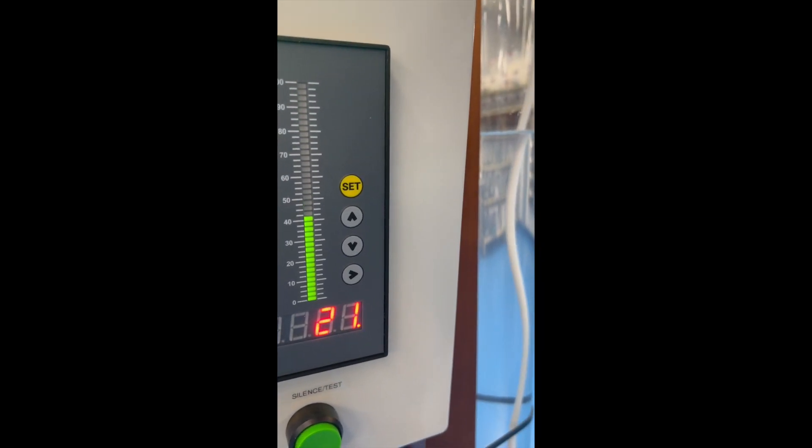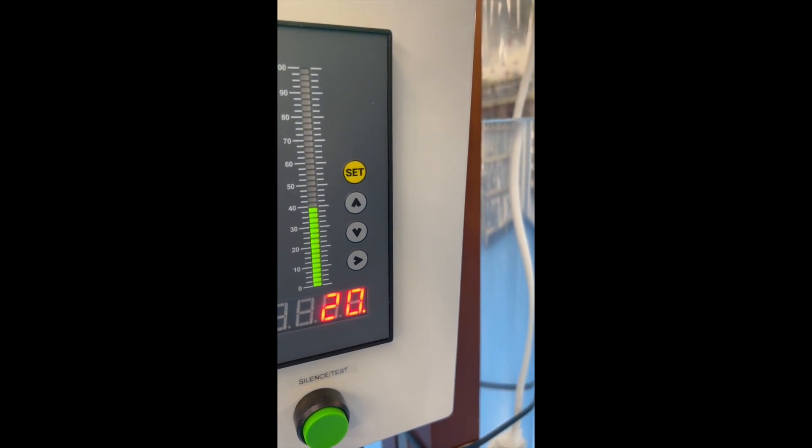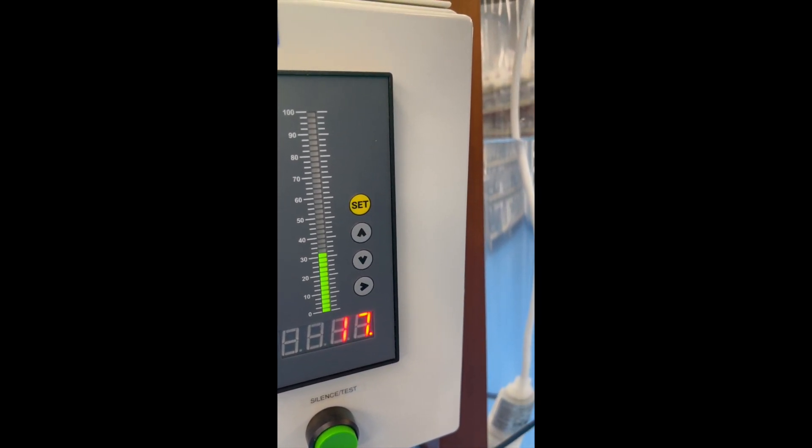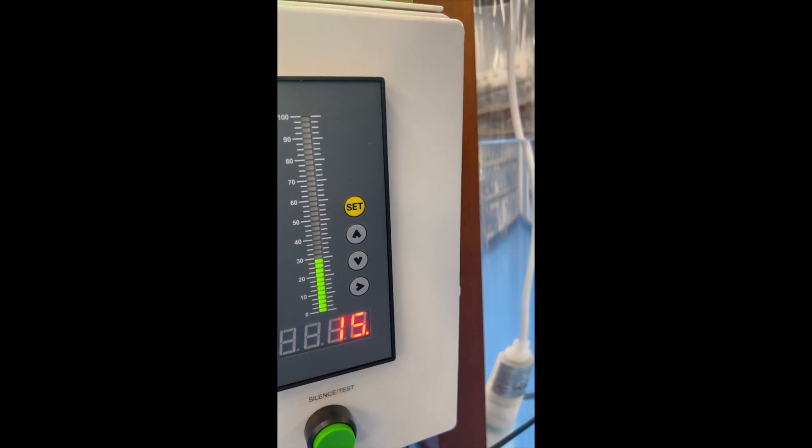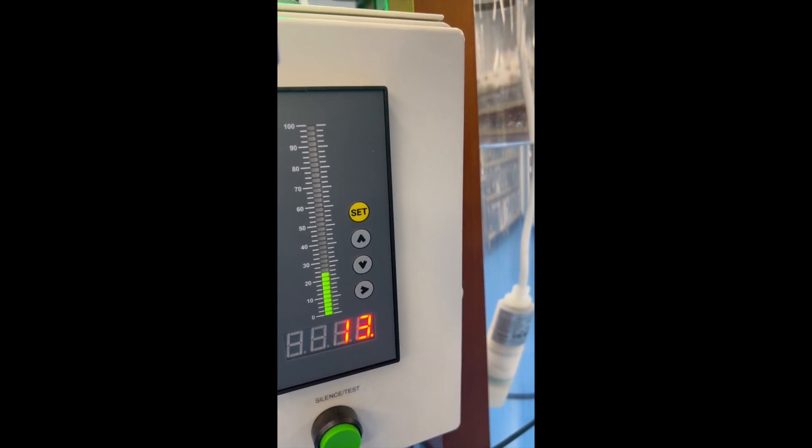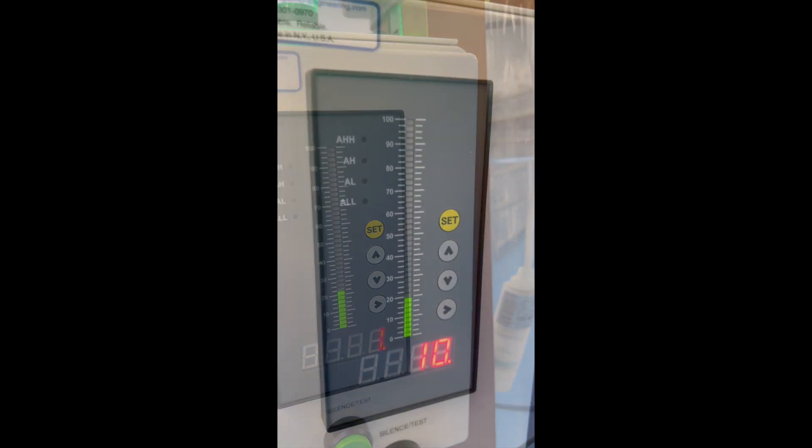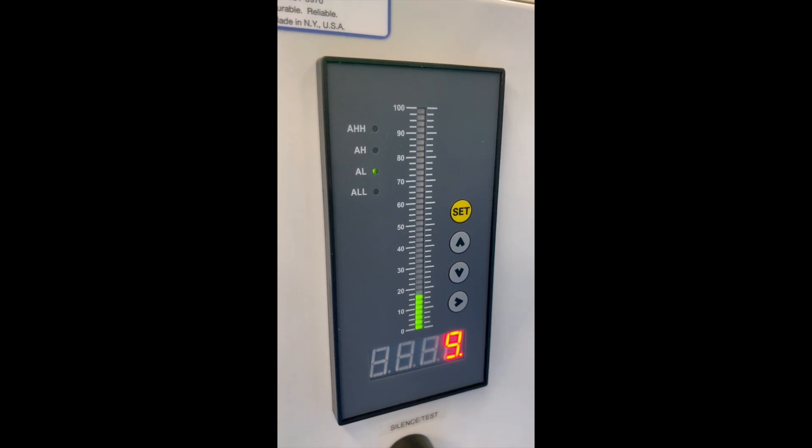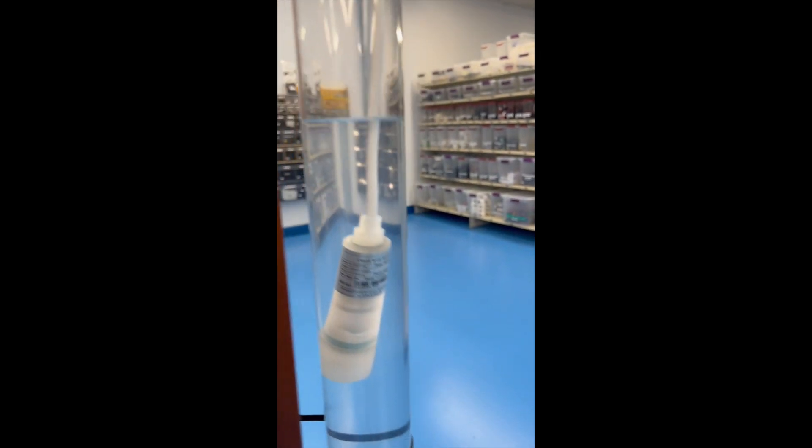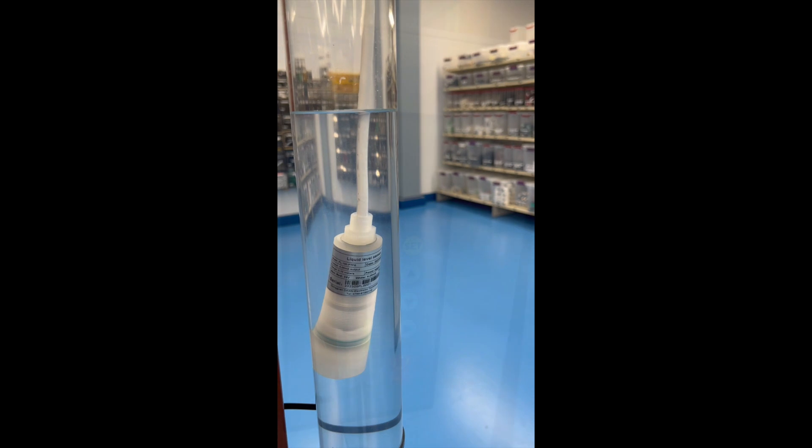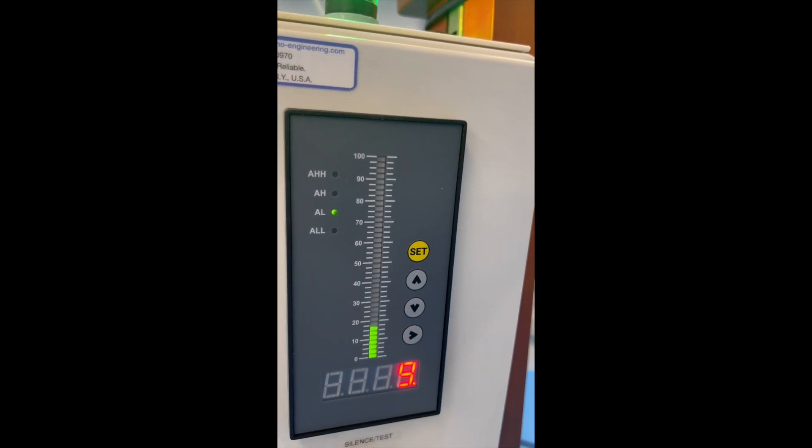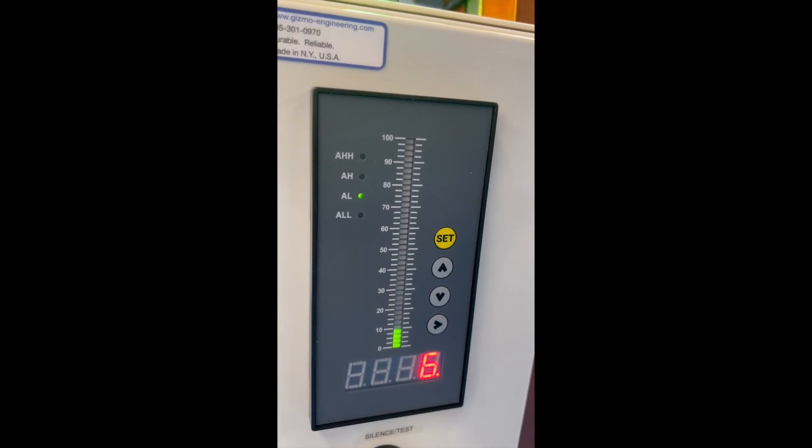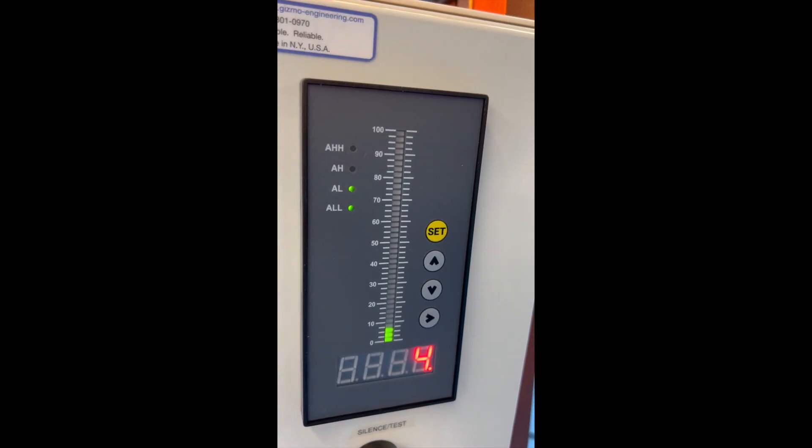I'm raising the sensor so that way there's less water column on top of the sensor and that's 17 inches of liquid depth and it's going down. I think I set it for 10 is the alarm level. So there we're at 10 and now we have the alarm low went off. So that's the yellow LED, no buzzer, I haven't configured it with a buzzer. You can see there's about 10 inches from the bottom of the sensor to the liquid level. So there's our yellow alarm and then we're gonna have a low low alarm right there.